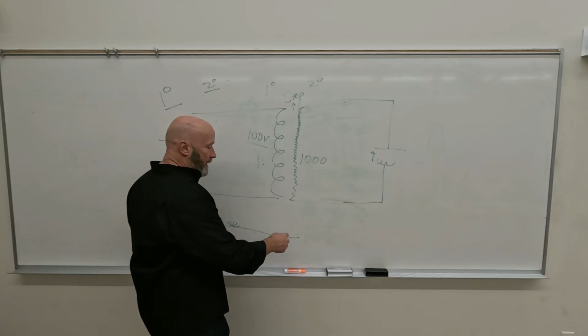So in this circuit down here, in our amperage circuit, what we're going to have is the opposite of this. We're going to feed this thing, and realistically, that 100 volts is not realistic. At this point, we're probably getting like 440 volts going into our X-ray machine, anywhere from 120 to 440 volts. But anyway, if it's 440 volts, that's too high. Electrons will jump across that gap, so we've got to reduce it. So we're going to use the exact opposite of this, and go with more turns on the primary side than we have on the secondary side. And in that case, our voltage decreases.